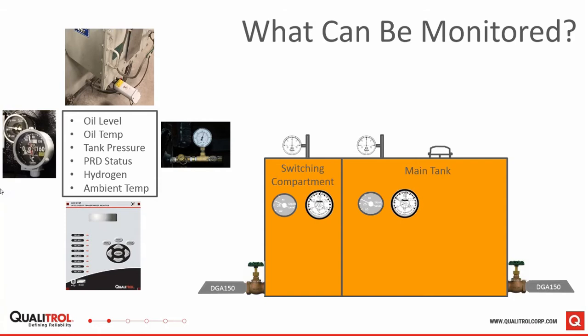We have Qualitrol, typically in North America. Most gauges on existing transformers, whether they have a Qualitrol name on them or not, were actually manufactured by Qualitrol. So we have an extensive capability to provide replacements for those gauges. Standardization over the years has been very difficult, and so if you look at 5 different transformers, chances are the gauges on those transformers will be different for at least 3 of the 5.